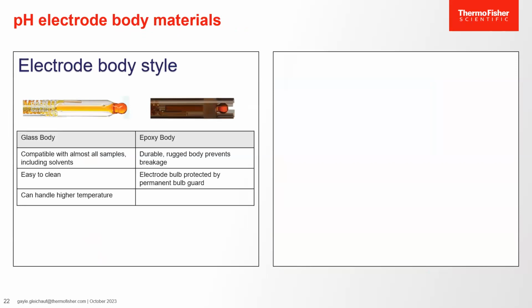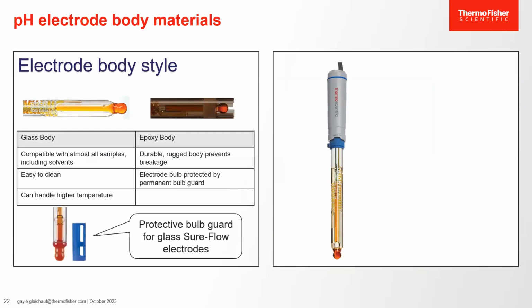pH electrodes come in glass or epoxy body styles. Glass body electrodes can be used in almost any sample, are easy to clean, and can handle higher temperatures. Some glass electrodes, like a SureFlow electrode, come with a removable bulb guard to protect the glass pH bulb from damage. On the other hand, epoxy body electrodes have a durable, rugged body that resists breakage. They have a built-in bulb guard to protect the glass pH bulb. So we can choose which body style best suits our needs.